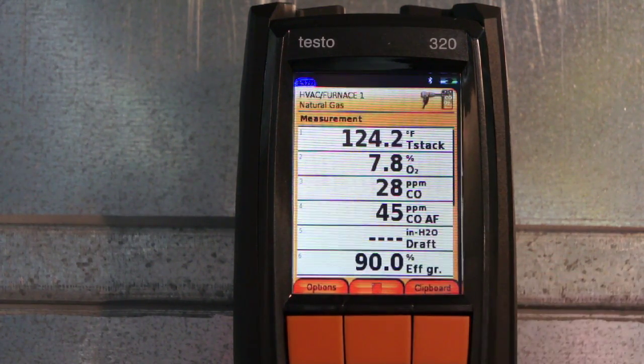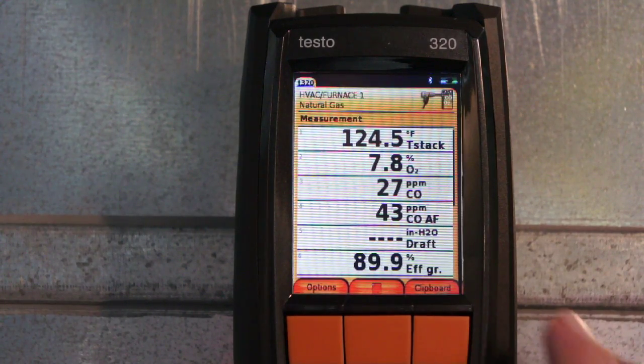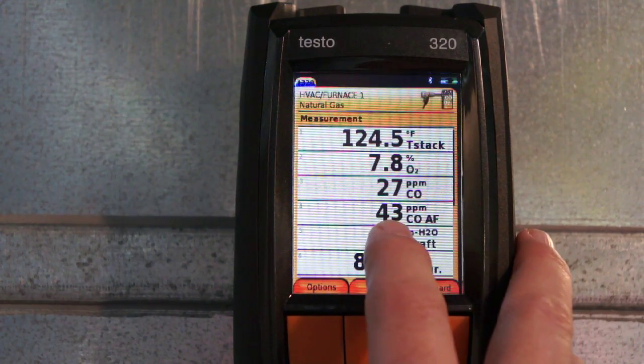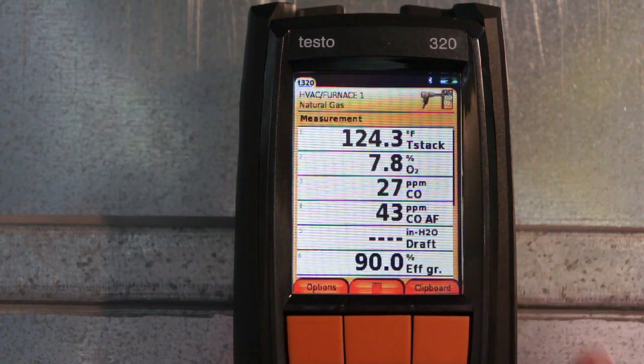My raw CO number I want to pay attention to, because I want to make sure that number is stable. I want to make sure that it's not climbing. If our CO is climbing, our O2 is dropping, right? That can be an indication that we have a combustion, dilution, ventilation problem. Also on my CO air free here, I want to make sure that it stays under 100 parts per million. If that's over 100 parts per million, we have a dangerous furnace that we want to get repaired.